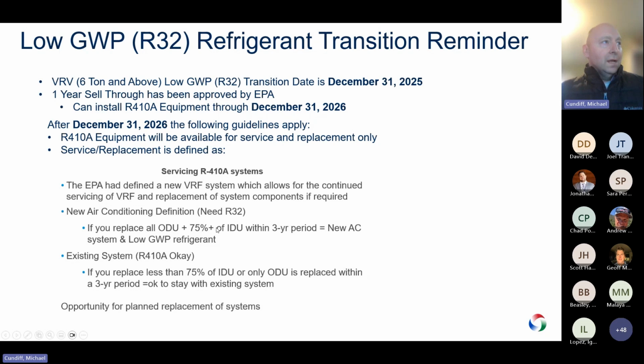The EPA has come up with some guidelines around that. For new air conditioning definitions, you need R32 after Jan 1, 2026. If you replace all the outdoor units and 75% of the indoor units within a 3-year period, it's considered new construction. You need R32. If it's less than that, you're okay with R410A, and we are going to continue to have R410A equipment around indefinitely.